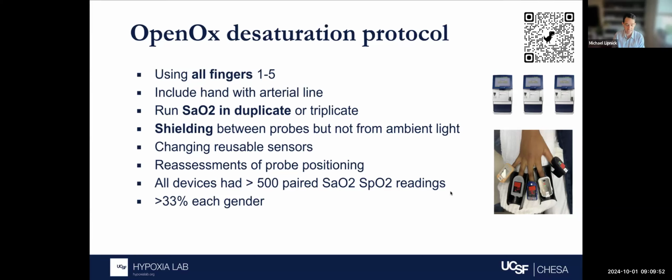I will say this was a significant factor that we saw, that keeping all of the probes in line and appropriately placed is challenging. In many cases, more so with devices that had a cable attached to them rather than these standalone fingertip devices, because the cables frequently would pull. And so we were taking a lot of care, as much as we can, to try and keep the cables in line with the finger.